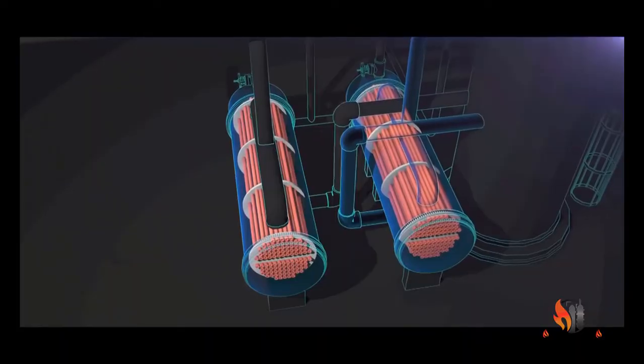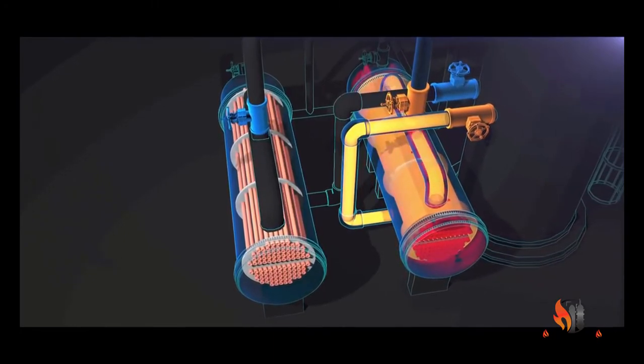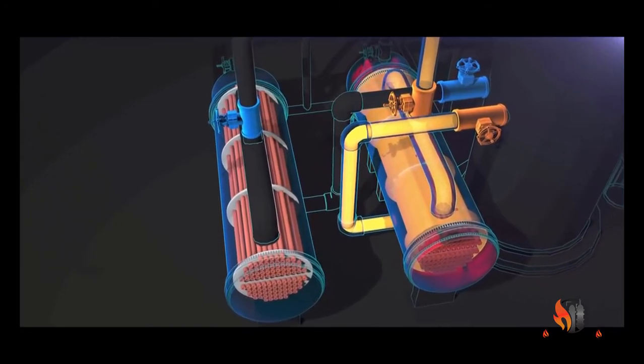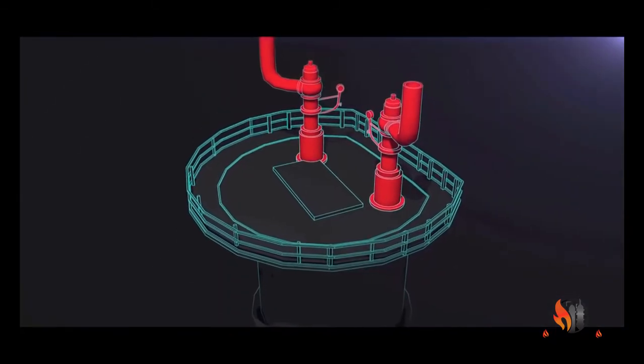When Williams installed the process block valves on the reboilers in 2001, they performed a management of change review to identify how this action affected the safety of the process. The CSB found, however, that Williams did not identify that the new valves could isolate the reboilers from their protective pressure relief valve.